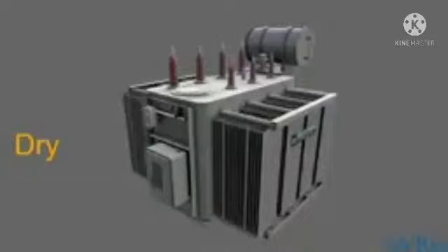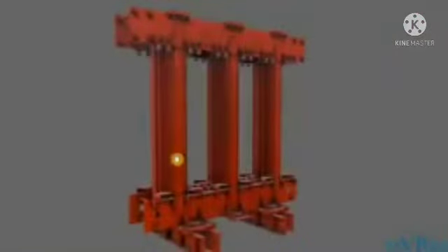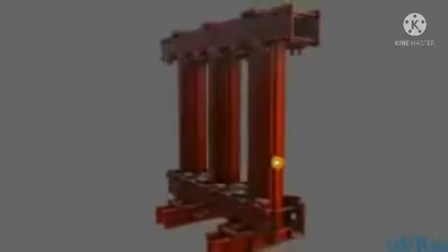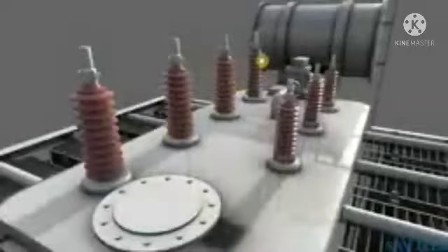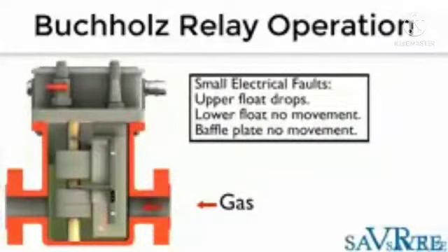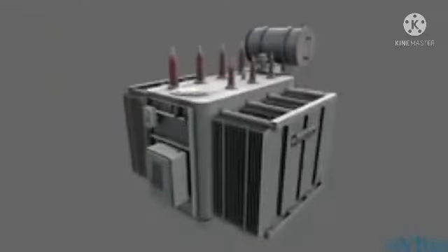Going to look at the dry type transformer, the hermetic type transformer, and the conservator type transformer. We're going to look at the transformer components such as the core and windings, and then we're going to look at some of the other components that you're likely to see, such as the bushings, gas actuated relay, temperature thermometer, and the dehydrator breather.